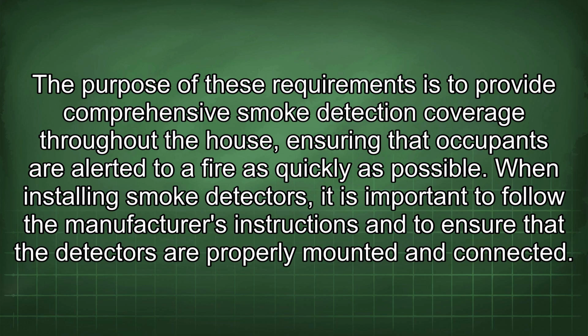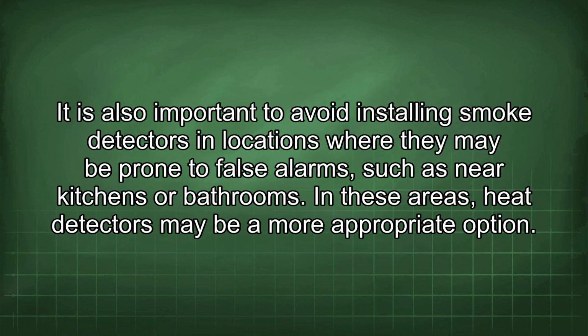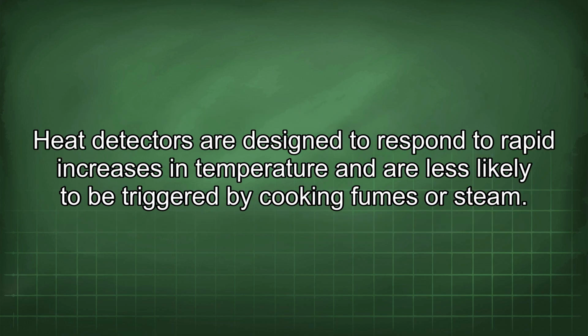When installing smoke detectors, it is important to follow the manufacturer's instructions and to ensure that the detectors are properly mounted and connected. It is also important to avoid installing smoke detectors in locations where they may be prone to false alarms, such as near kitchens or bathrooms. In these areas, heat detectors may be a more appropriate option.